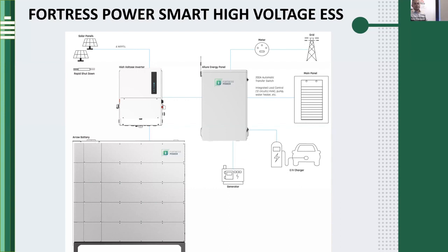With the high voltage system, most of the expensive components that are inside a hybrid 48 volt inverter are going to be in our smart energy panel instead. So as the system gets larger in size and you need multiple inverters, high voltage inverters are lower in cost than their 48 volt counterpart. Thus, the larger the system, the more cost efficient the high voltage ESS will be in terms of cost per kilowatt hour.